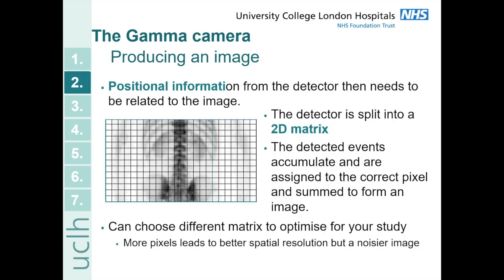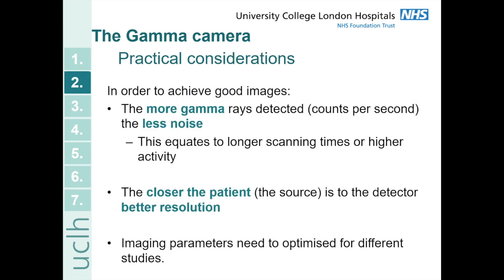Now that we've detected the photons we need to use the positional information from the detector to form the image. The detector is split into a 2D matrix and detected events accumulate and are assigned to the correct pixel within that matrix, then summed to form the image. You can choose the matrix size to optimize for your study — more pixels give better spatial resolution because each pixel will be smaller, but you'll end up with a noisier image because you have fewer counts per pixel. Practical considerations include: more detected gamma rays mean less noise; keeping the detector closer to the patient gives better resolution; and imaging parameters need to be optimized for different types of studies.